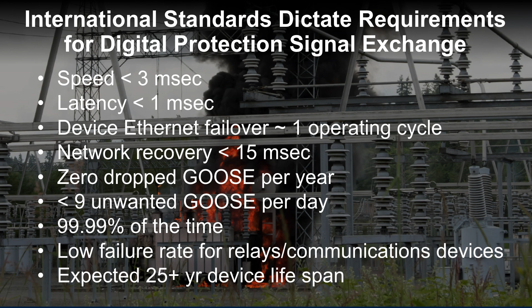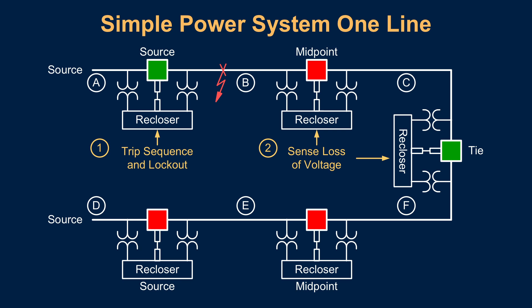You may not be familiar with this, but this is a typical one-line diagram of a very simple distribution line. This is a power line, not a network communications diagram. What I'm showing here is what that distribution system would look like in terms of the power going through a line, with the power system itself asking, how do I minimize the outage to a smaller geographical area? So there are decisions being made, in this case shown as recloser controls, that are talking to one another and saying, I don't want to take out that entire path, that entire loop. I want to take out maybe just a small part where the particular fault is injected onto that power line. Think about it as microprocessor-based circuit breakers on a larger scale, saying, how do I minimize the outage that might affect a larger group of power consumers?